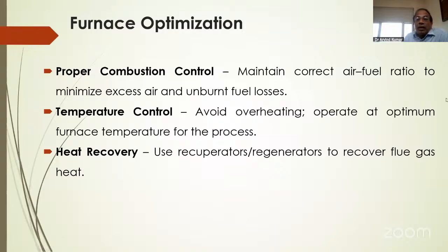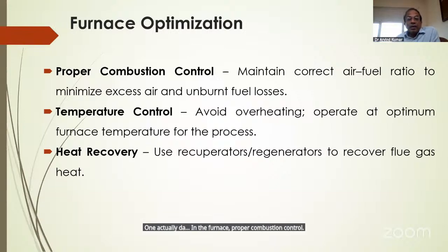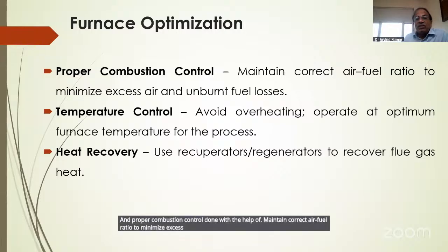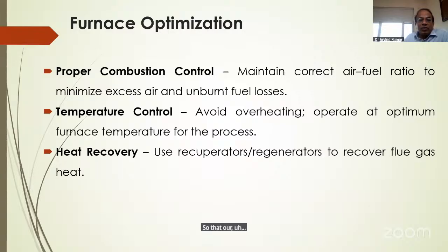Now, in the furnace thermal energy system, in furnace optimization, proper combustion control is done with the help of maintaining the correct air-fuel ratio to minimize excess air and unburned fuel losses, so that our unburned fuel losses are minimized. Temperature control: avoid overheating and operate at the optimum furnace temperature for the process. Heat recovery: use recuperators, regenerators, or heat wheels to recover flue gas heat for further use in the system.